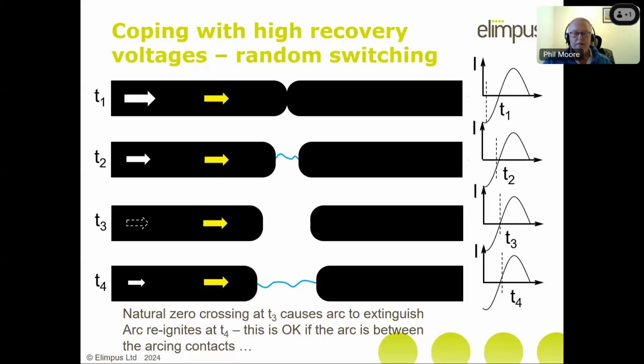And you might say, okay, so the arc reignites, so what? Well, the answer is that when the arc reignites, you don't know exactly where that arc's going to be. You might think surely it must occur across these two contacts, as they are pretty close together. Well, think about lightning, particularly pictures of lightning that show its progression. It's very random and chaotic, and it's exactly the same in a circuit breaker. When the arc reignites, it doesn't reignite along all of the path simultaneously. It reignites in little bursts until it eventually bridges the whole gap.